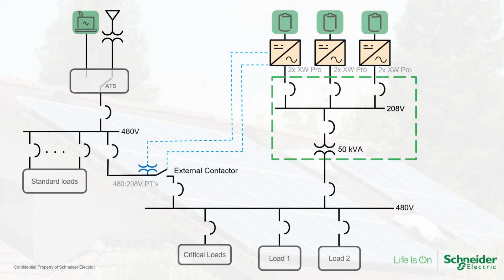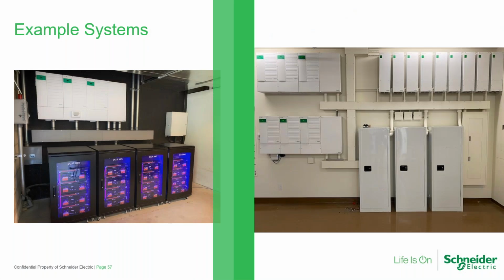Here's a sample system that uses 6 XW Pro for a 40 kW system that uses an external AC contactor for 480 volt loads. Note a small transformer is needed for sensing. Here are 2 sample XW Pro 3-phase systems currently deployed in the field. The one on the left is an AC coupled 20 kW 3-phase system. The one on the right is a 40 kW 3-phase system with 9 high voltage MPPT units for a DC coupled solution in Hawaii.